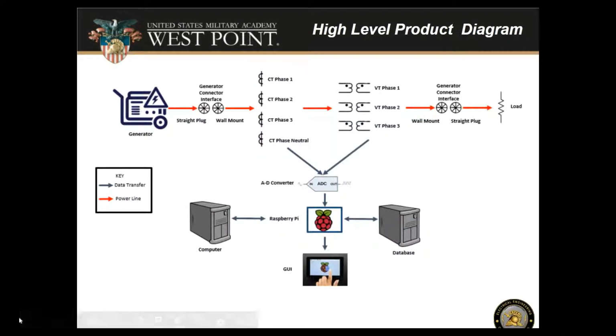The product background slide describes the why. The high-level product diagram describes the how. The TAC-Gen will measure the output of the military generator using straight plug and wall mount connectors. Current transformers will measure its current, and voltage transformers will measure the voltage. The A to D converter outputs digital signals, and using C++ Fourier transform algorithms, we are able to calculate the phase and amplitude of the power. We can then do three things with this data: store them in a database, display them on a GUI, or analyze the data on a computer.